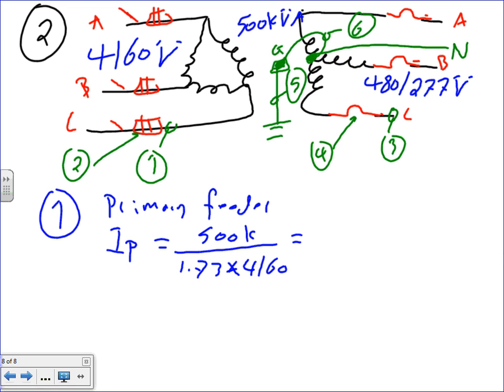In smaller communities, the top notch right now is 13.8. Okay, 4160. Actually, my transformer, I forgot one. It's a 1500. Can you guys do me a favor? The transformer is a 1500. Just add a 1 here, will you? Change it to 1500 instead of 500, just to make it make sense on the medium voltage side.